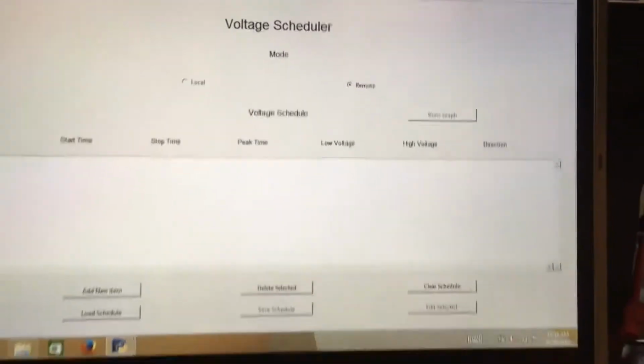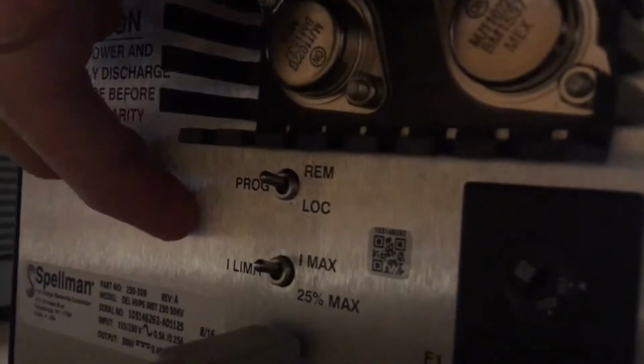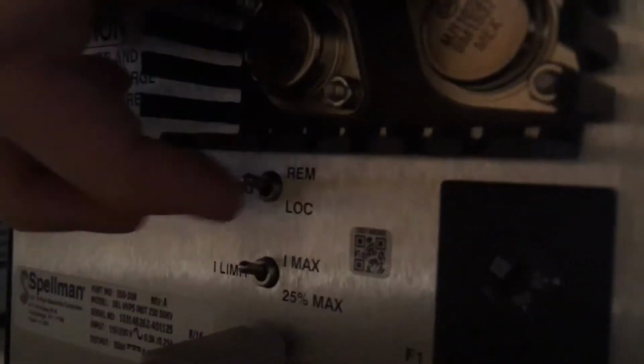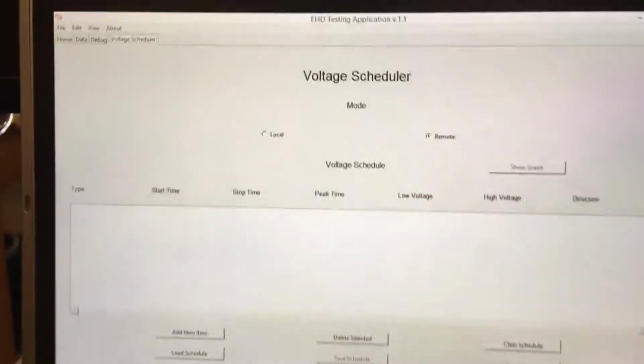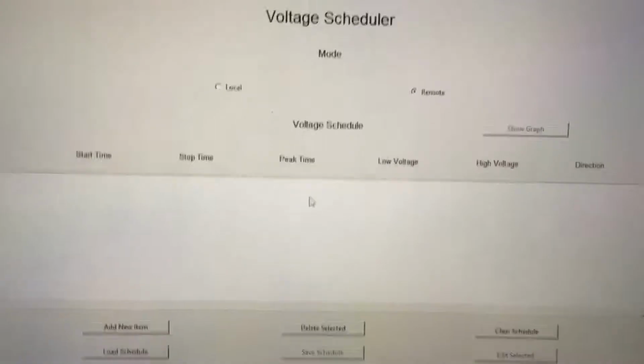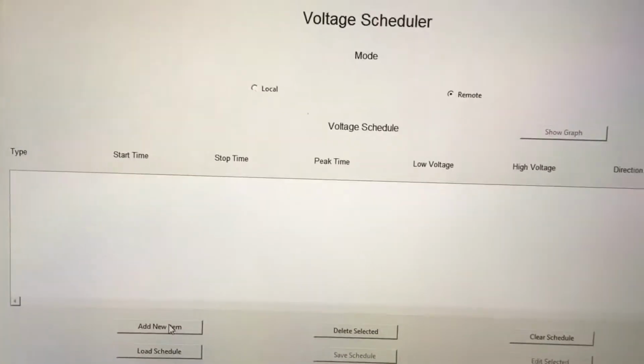First thing you do is make sure that remote is selected, and that will bring up a dialog box also, and it will be asking you to make sure that the switch between manual and remote has been switched. That is this top switch here. Make sure that is on remote before starting a test, or the voltage supply will not be seen by the program.